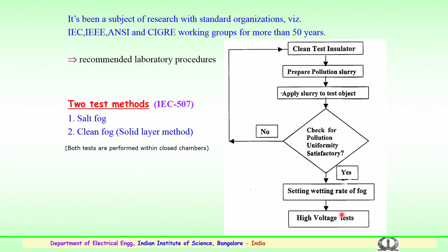The procedure involves first cleaning the insulators, then preparing a pollution slurry as per the standards. This slurry is applied to the test object, and the surface is checked with equipment to see whether the coating is uniform. If uniform coating is not achieved, the procedure is repeated. If it is, then the wetting rate of the fog is set. The fog, cold fog or steam fog, makes the insulator surface wet, high voltage is applied, and the pollution tests are performed. This flow chart describes the method adopted for laboratory conditions.